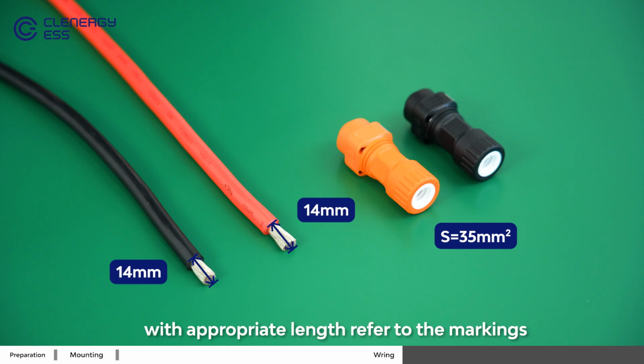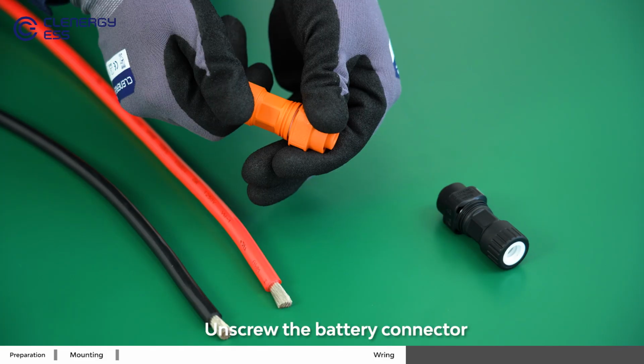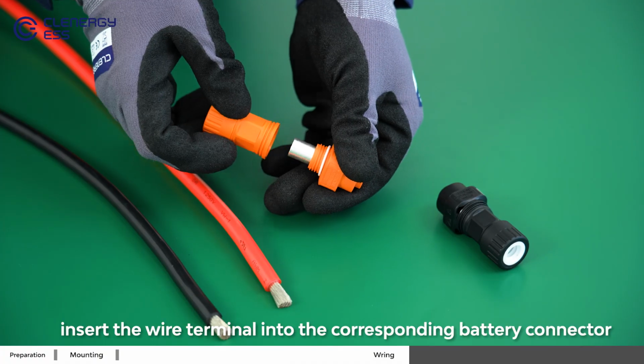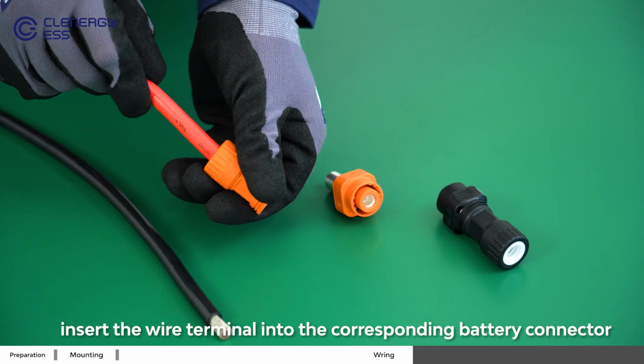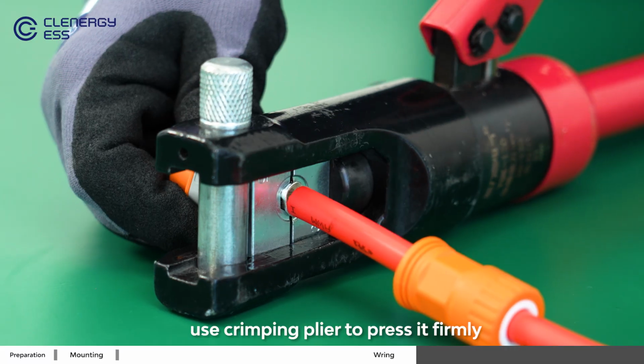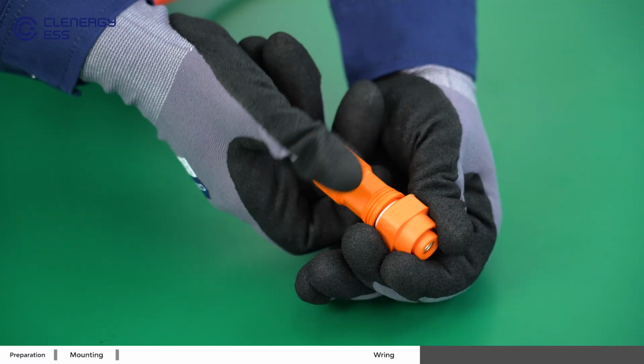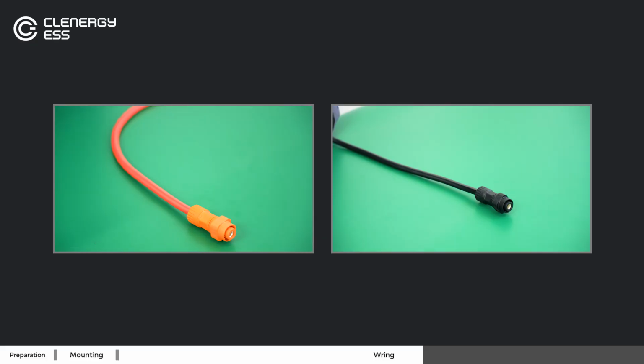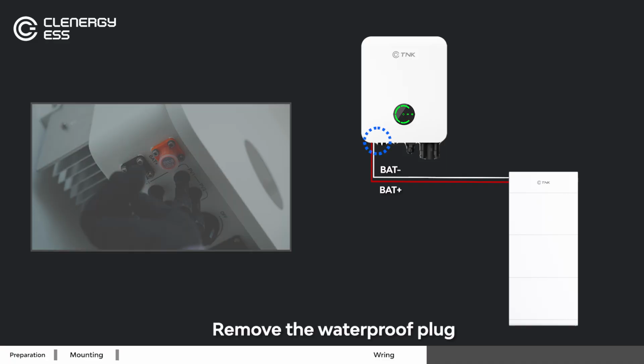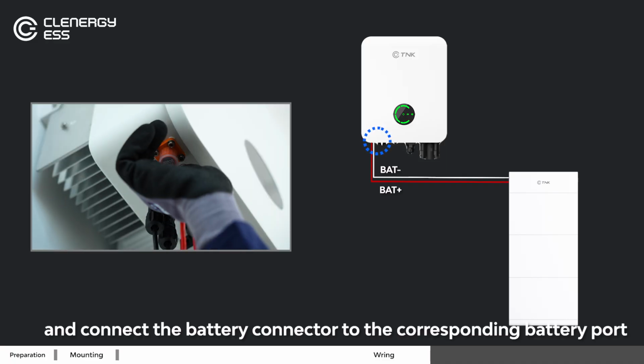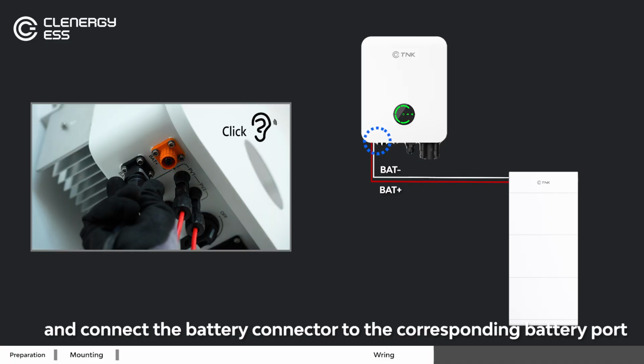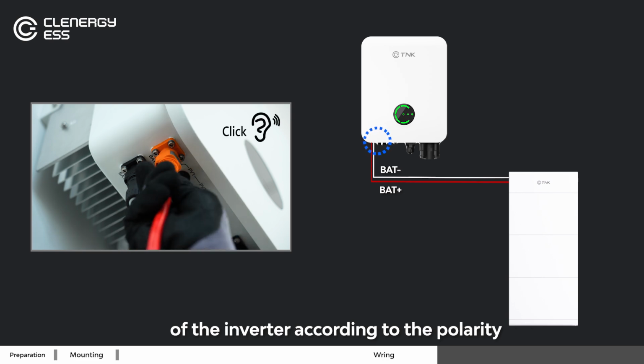Refer to the markings. Unscrew the battery connector. Insert the wire terminal into the corresponding battery connector. Use crimping plier to press it firmly.